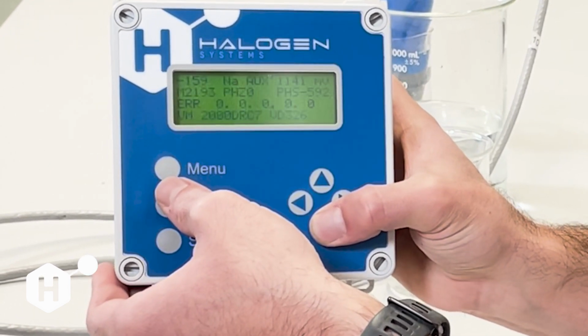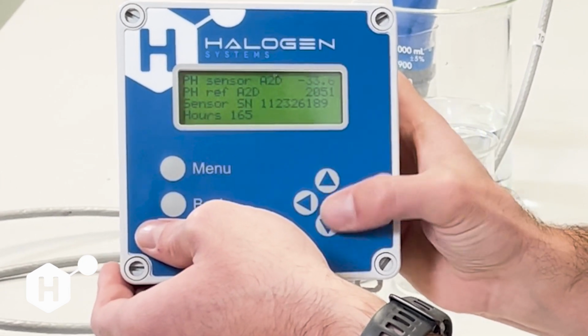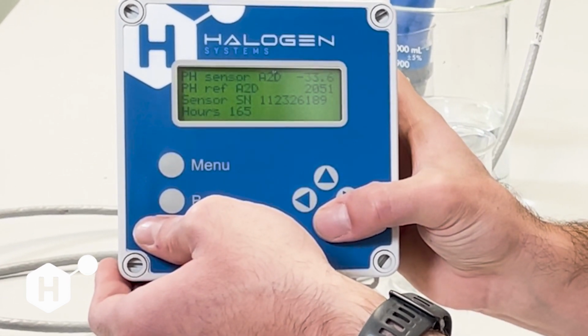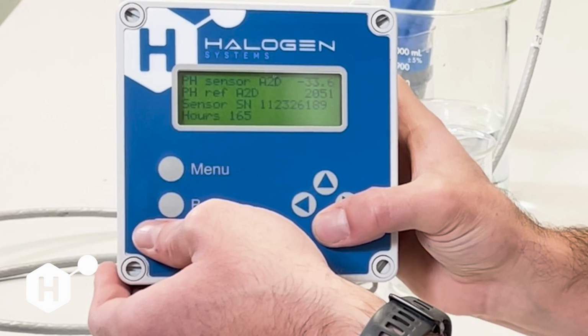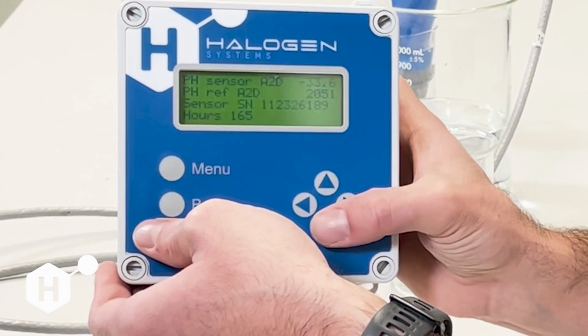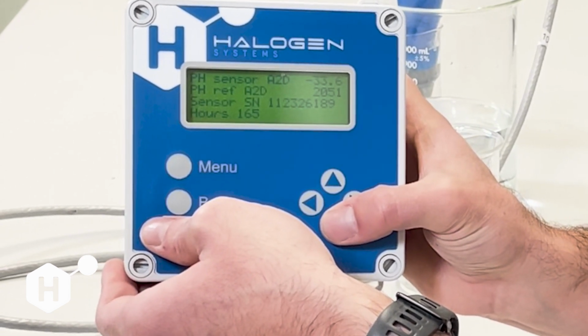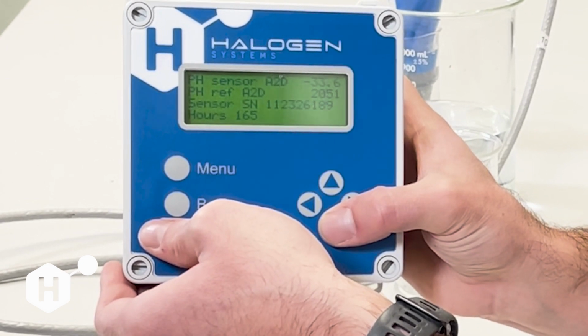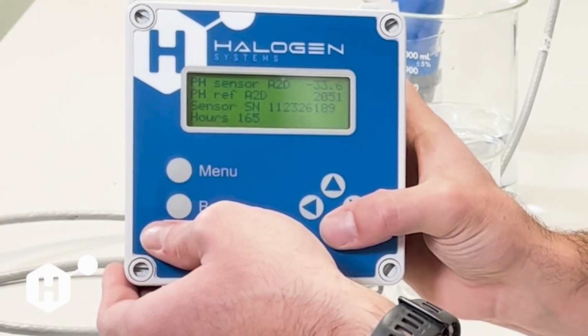So I'm going to give this one more cycle. So I've seen negative 31.6 and negative 33.6. I'm going to give it one more cycle and see if we get much change. I'm looking for changes less than about 2 millivolts between cycles before I'm going to initiate a calibration.